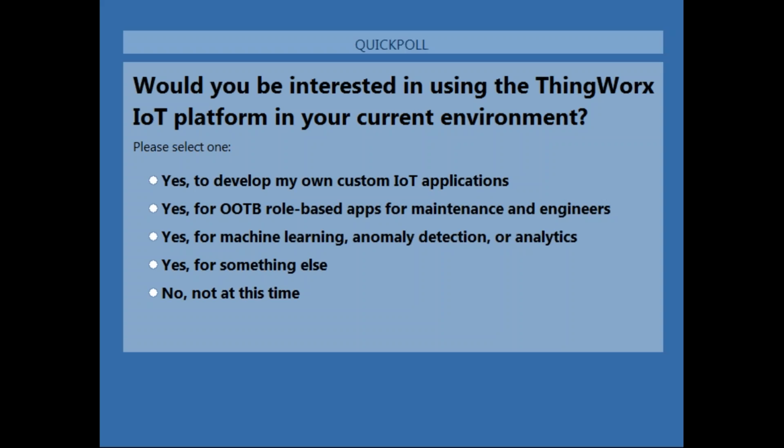We had some questions about the speed of ThingWorx updating data and scan rate. So the scan rate I showed from the ThingWorx platform is per second, Douglas. And Michael asked, how fast can ThingWorx update tag data? So Michael, right now we have specs. We're confident to say you can do at least 10,000 tags on one single asset or entity that you have defined in the platform at a 1 second rate easily. Or if, say, you have 100 assets defined, each with 100 items attached, you can do the 1 second rate. We can handle sub-second rates, no problem there.